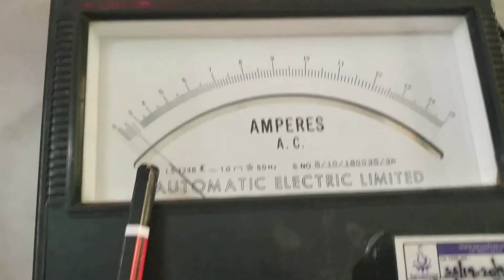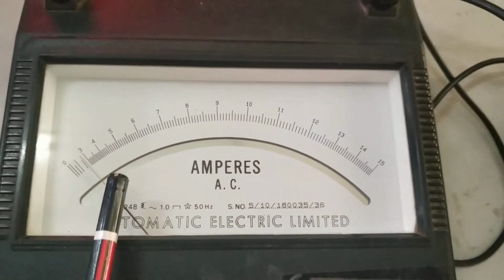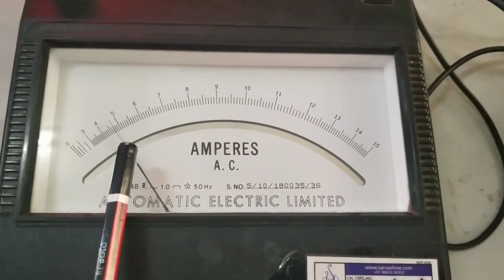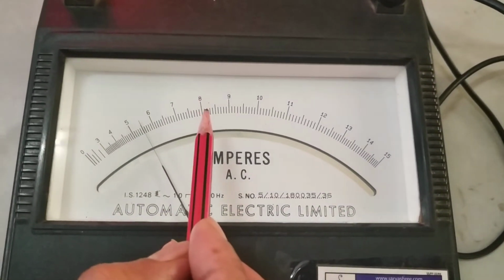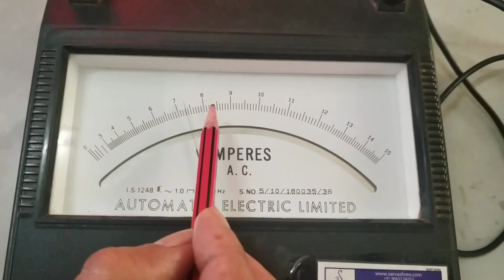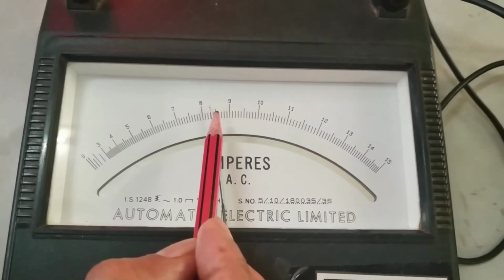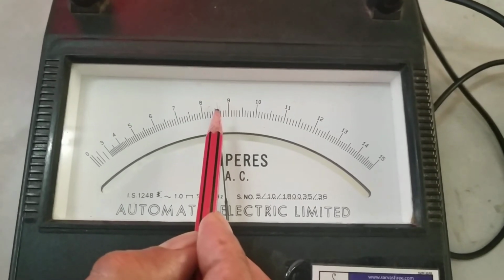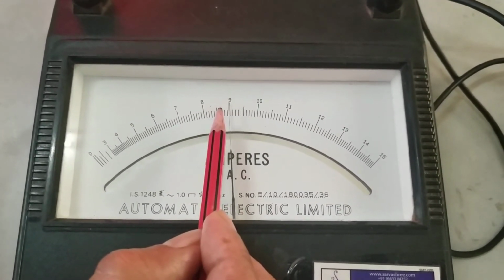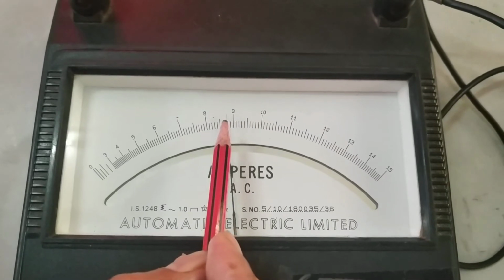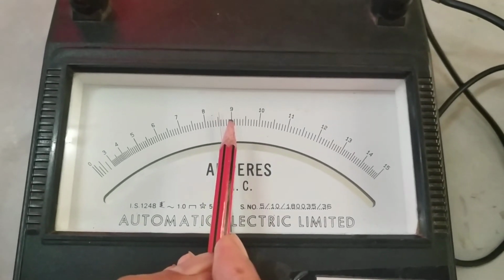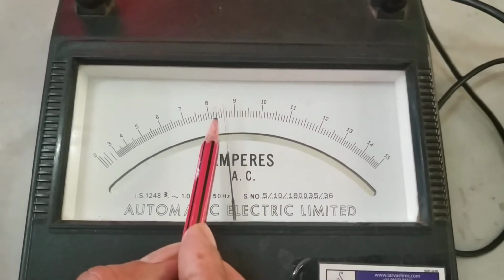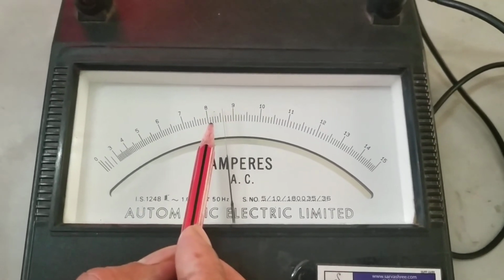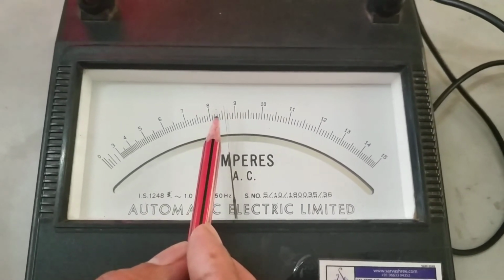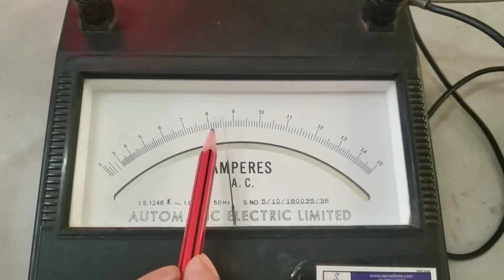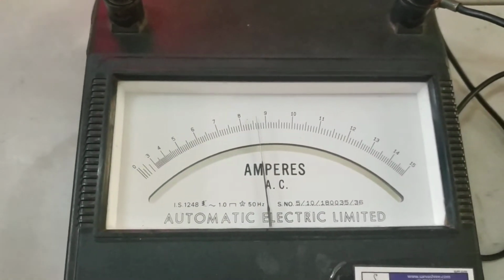The rated current was calculated as 8.69, so we need to apply a reduced amount of voltage to get the rated current in the ammeter, that is 8.69. It is approximately 8.67. Okay, now we are getting 8.69 ampere. We should not increase the voltage further; we need to leave it and take all the meter readings for the short circuit test.